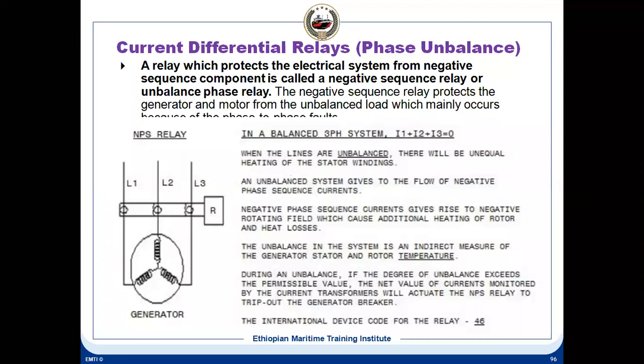Here you can see the CTs. There are 3 CTs whose output is connected to a relay here. Whenever there is an unbalance between these 3 phases, the relay will get activated and it can trip. Whenever the lines are unbalanced, there will be unequal heating in the stator winding. An unbalanced system gives rise to the flow of negative phase sequence currents, which create a negative rotating field, causing additional heating of the rotor and heat losses. So an imbalance in the system is an indirect measure of the generator stator and rotor temperatures.